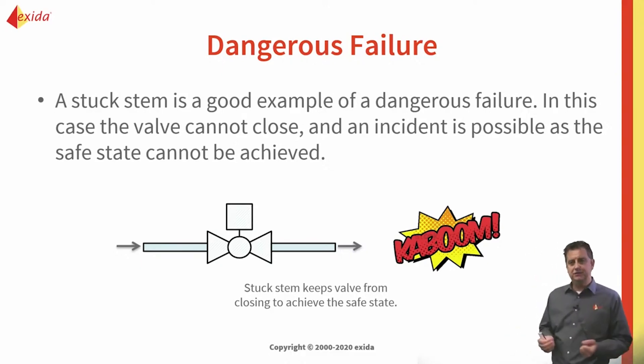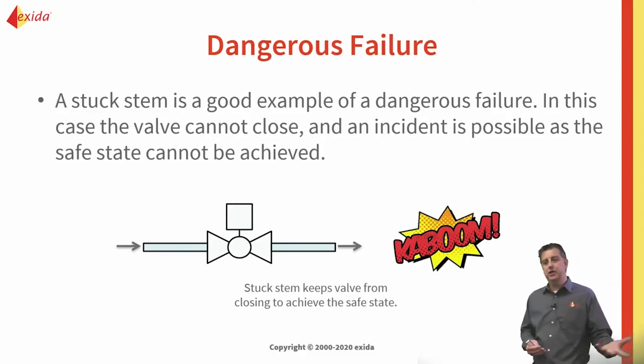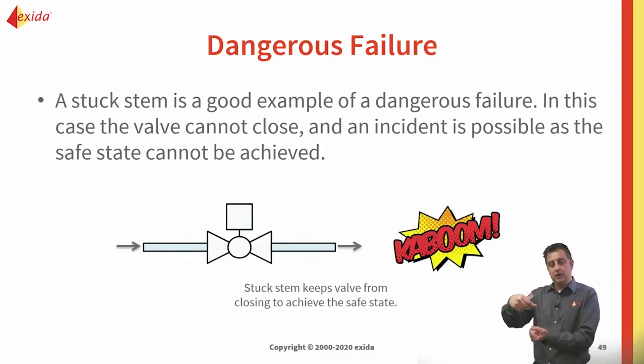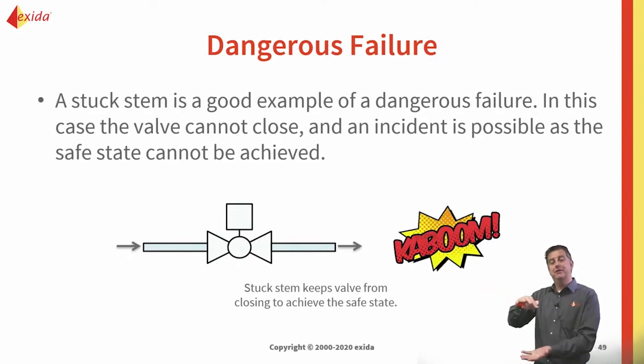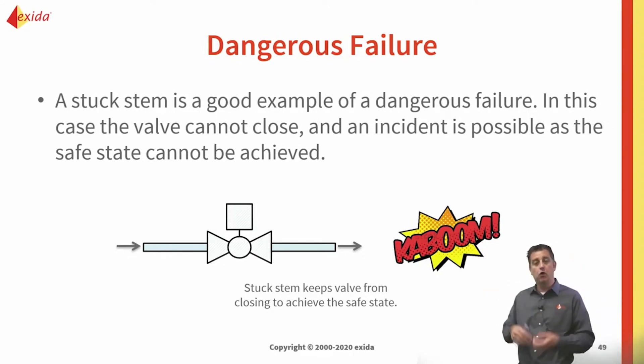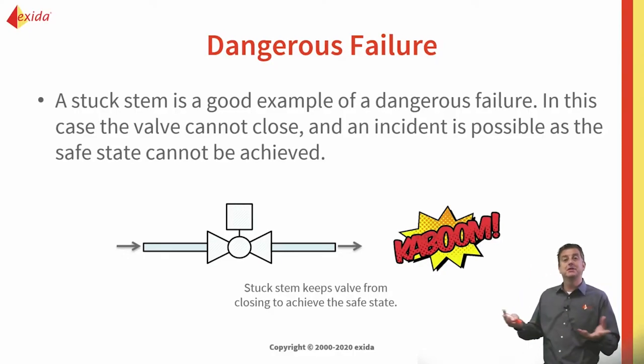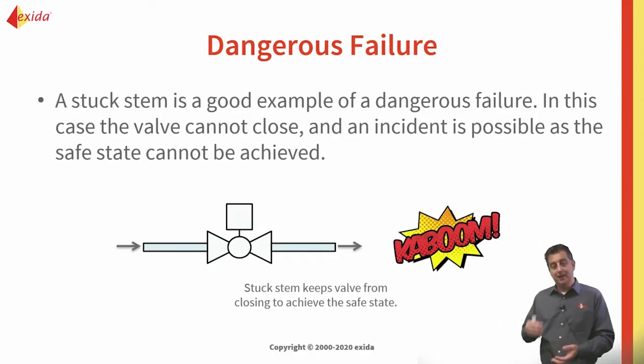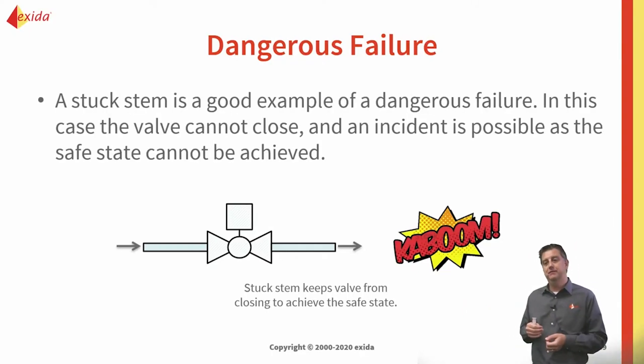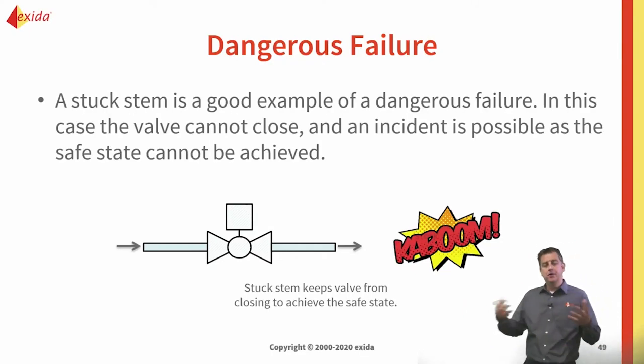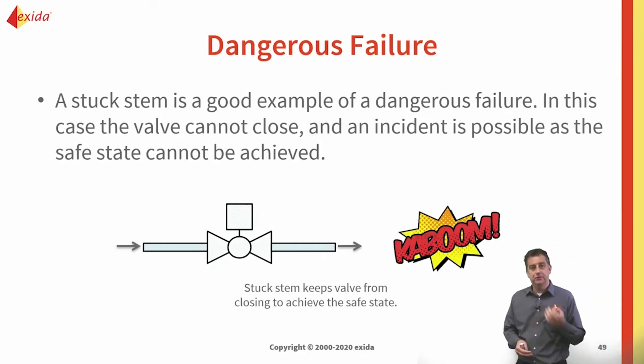That would be a dangerous failure. Examples include a stuck stem — you can remove the pressure from the actuator, maybe it's a spring return actuator, but the valve just sits there and doesn't do anything. Or maybe the spring in the actuator is broken and there's no force to drive the valve to the safe state. Those are two examples of dangerous failures.